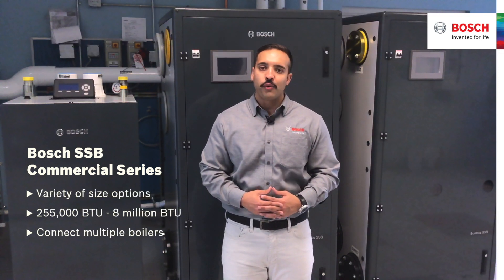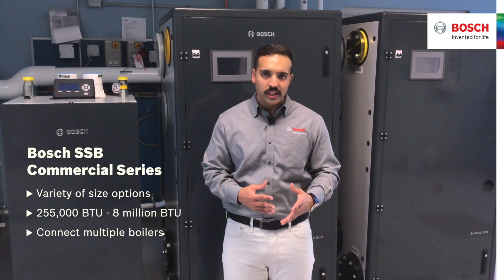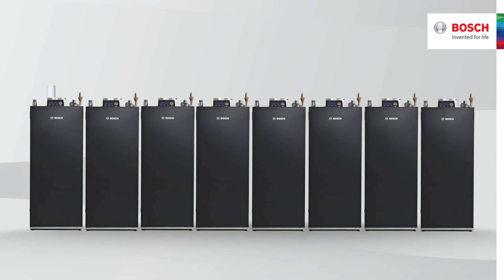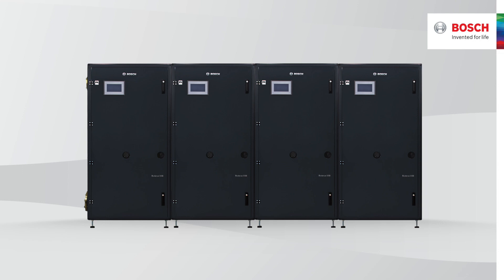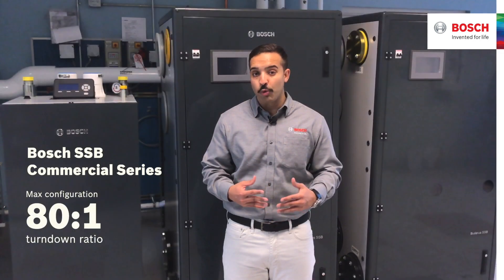We offer size options for commercial applications ranging from 255,000 BTUs to 8 million BTUs, with each unit having the ability to connect multiple boilers in a cascading system using their built-in programming and communication. This allows a max configuration to have an 80 to 1 turn down ratio.